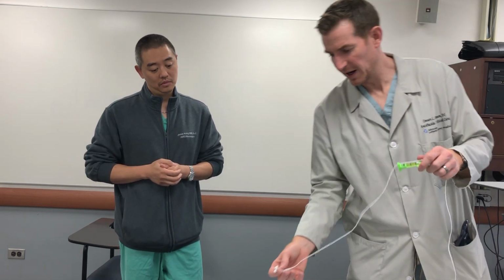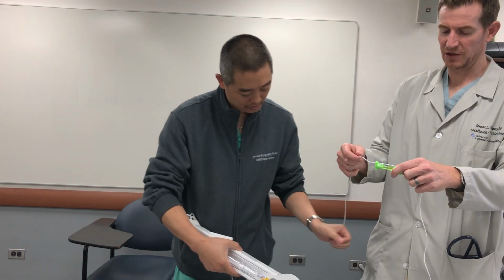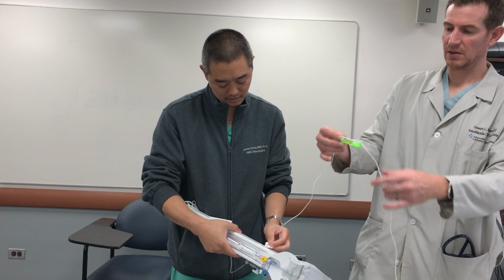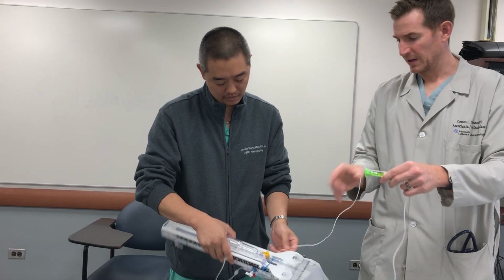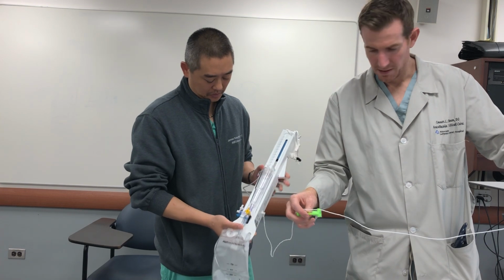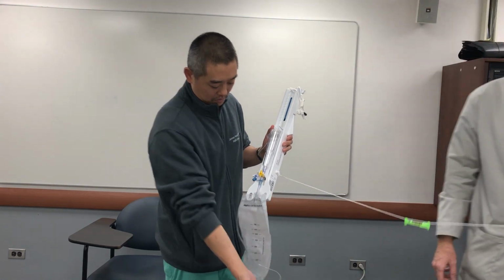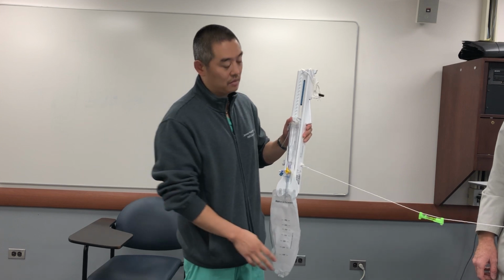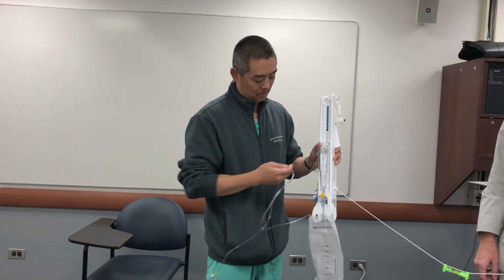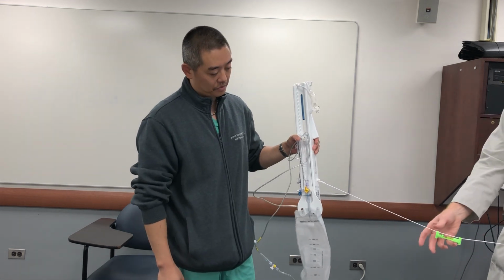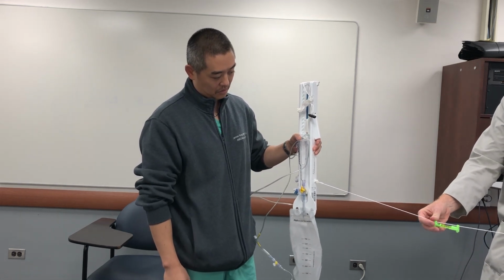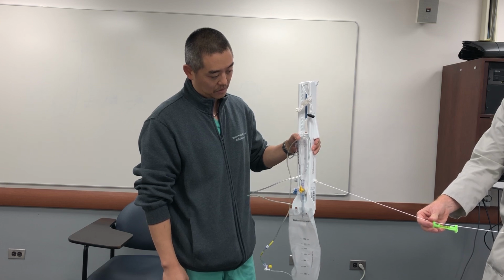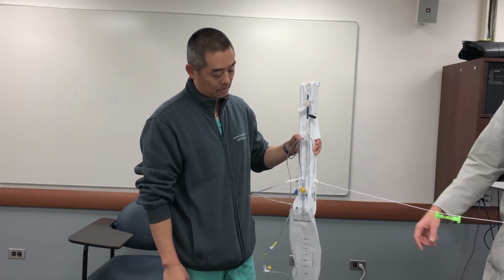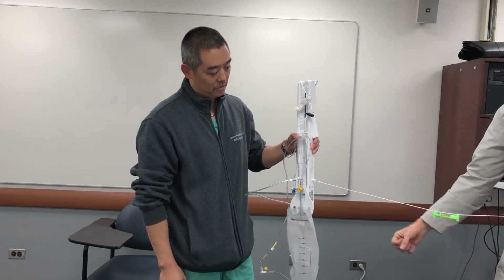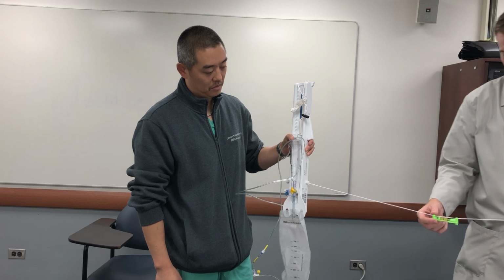Once you get into the operating room, you want to level the system to the patient. This kit has a leveling bubble, like your typical level, snapped into place. You typically do this at the external auditory meatus. This little ring goes to the patient's ear when they're lying flat, and this little bubble is supposed to be level, like a regular level. If you're too high or too low, it's not going to drain properly, or it's going to drain excessively. That's how we set it up.